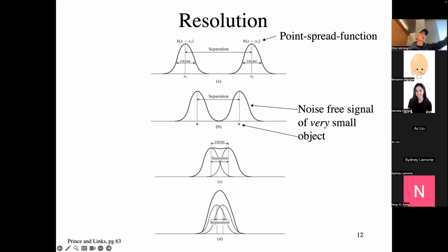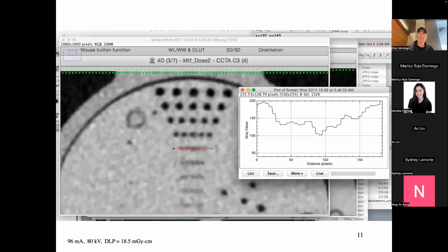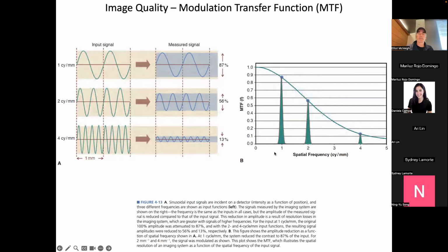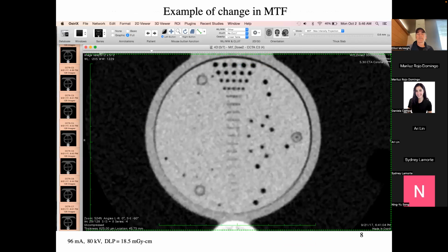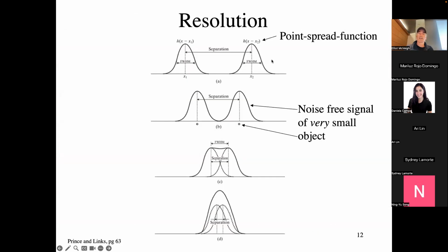And looking ahead to those of you who are comfortable working in either Fourier space or real space, the point spread function, when you take its Fourier transform, you get the modulation transfer function, right? So the modulation transfer function, remember, when we go back and look at it, the units on the axis are spatial frequency. So it was in cycles per millimeter, cycles per centimeter, something like that. The point spread function, its units are in space, right? So this half height here, which gives me the full width at half max, say, of this thing, is in millimeters.